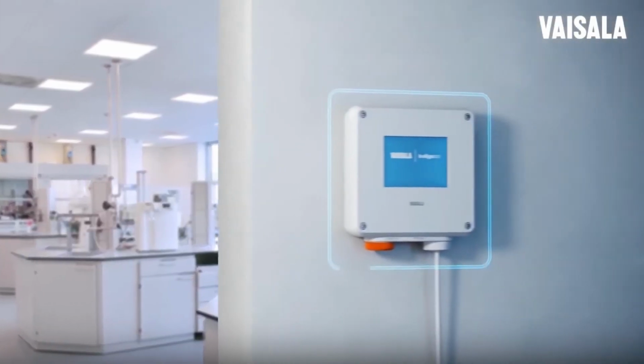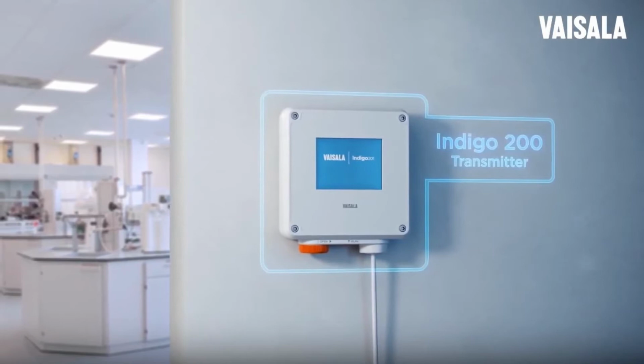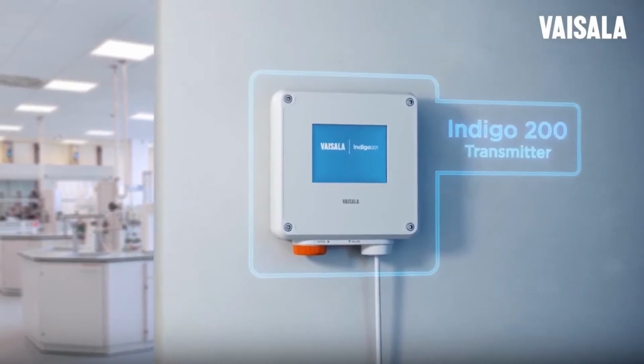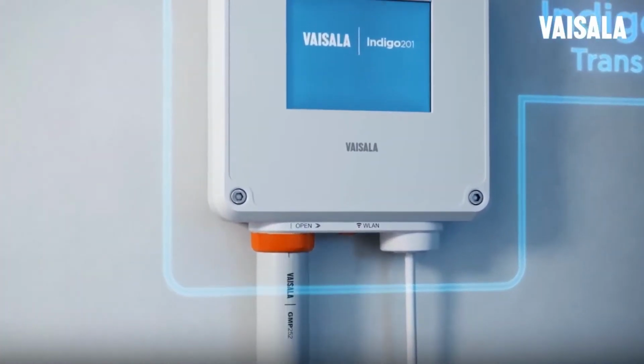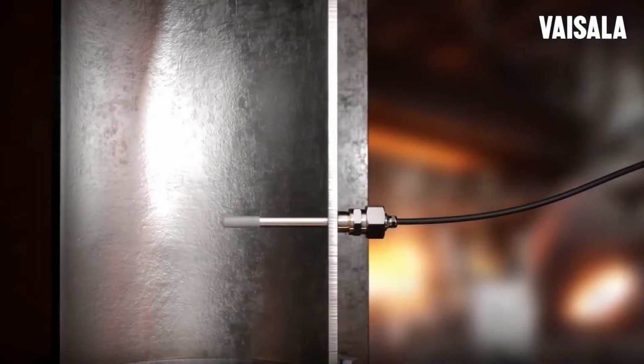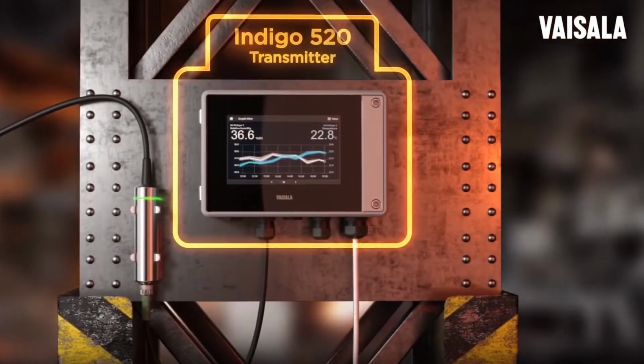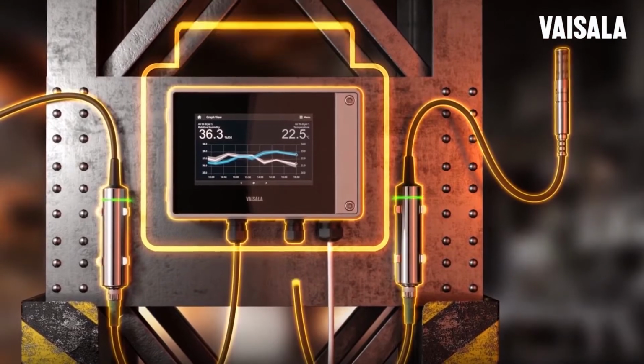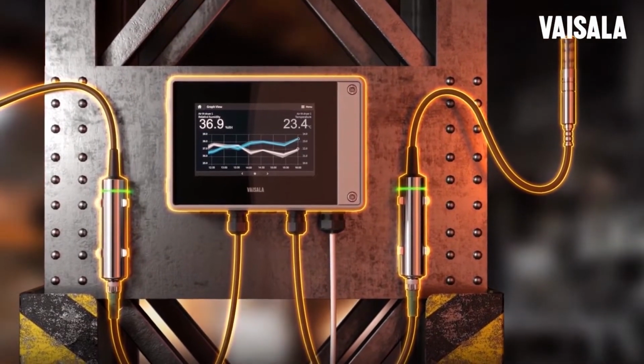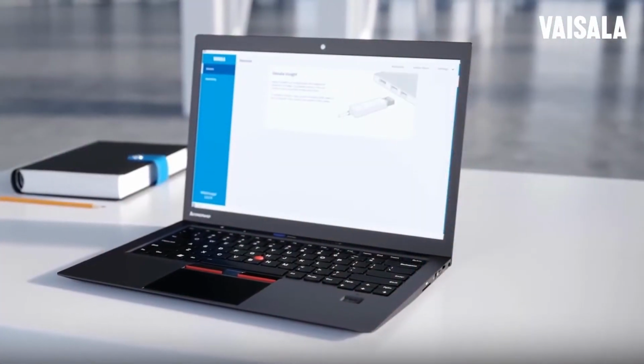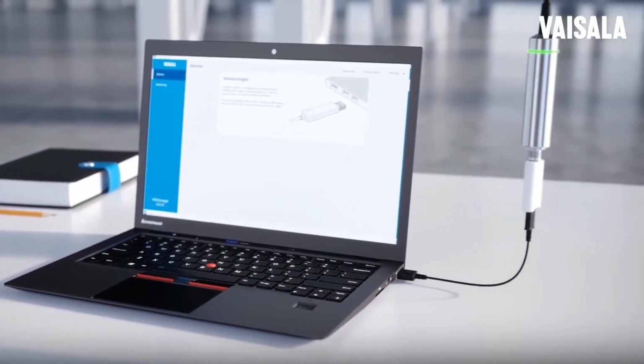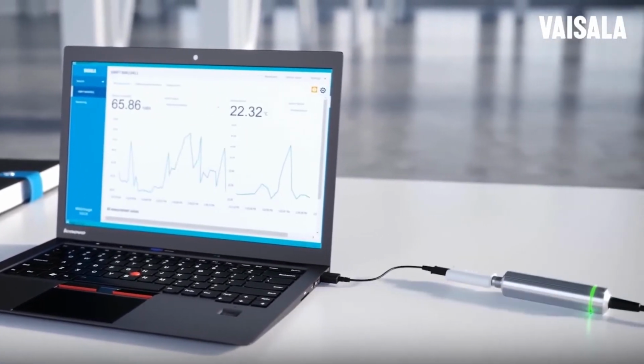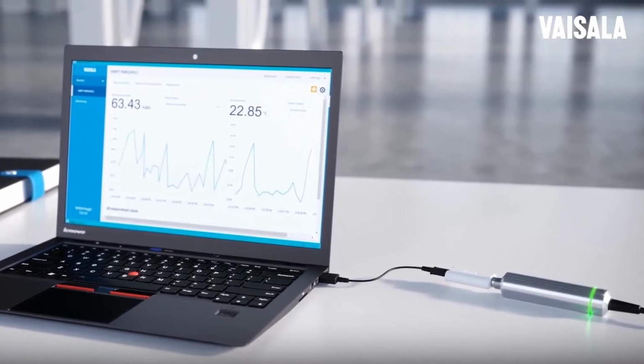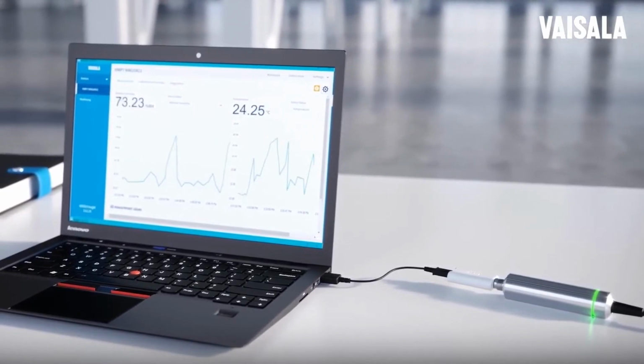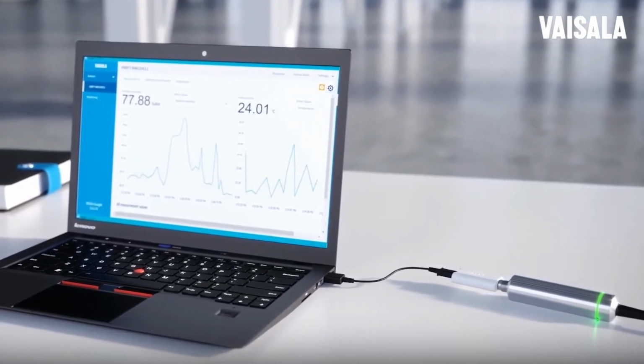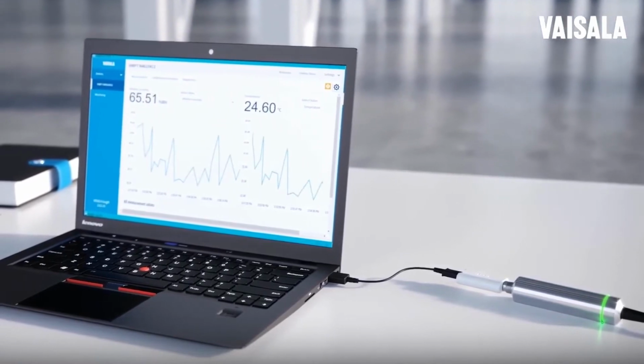We then pair those sensors with Indigo transmitters, and the Indigo transmitter allows you to modify and customize based on your specific application. Some of those advantages allow the ability to swap probes out in the field while they're powered up and still running. This allows you to send units back to us or to your own lab for calibration, minimizing downtime. And by doing this, you don't have to shut your process down. You get the stability and the reliability over a long period of time by doing this calibration without taking them down and swapping them out with the host transmitter.